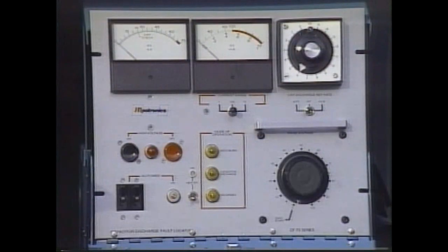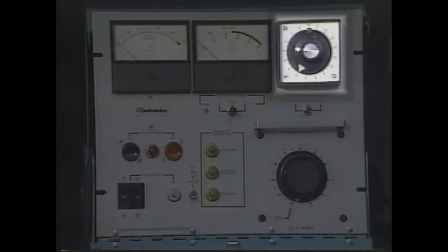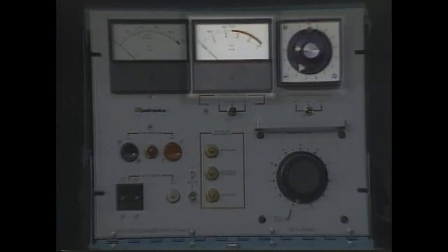At this point, we should take a close look at the controls that are on the front panel of the thumper we are using. At the upper right, we have a timer that has been set to trip every 6 seconds. The timer tells the thumper to discharge a pulse into the cable, so our thumper will be thumping every 6 seconds. The meter in the top center is our current meter.